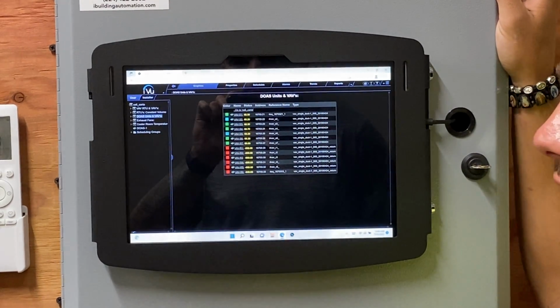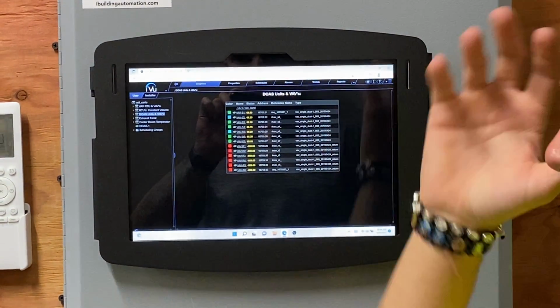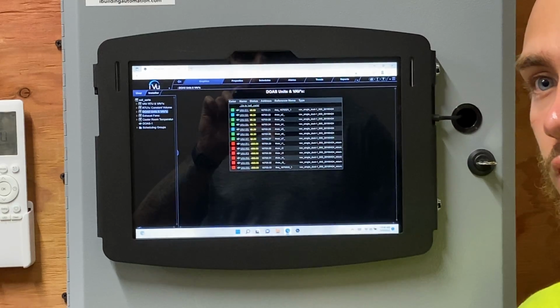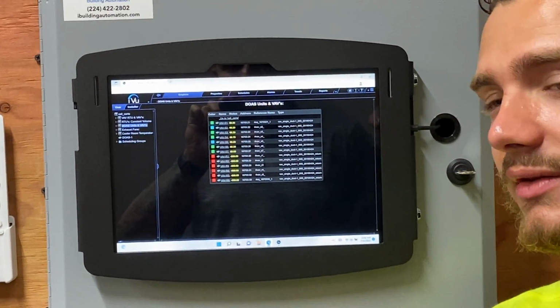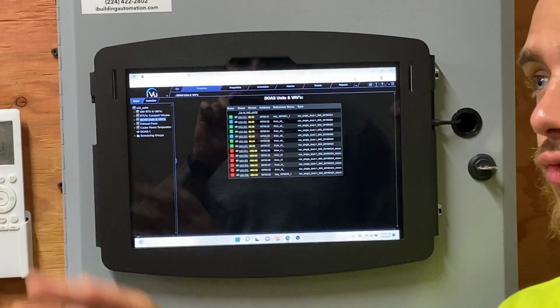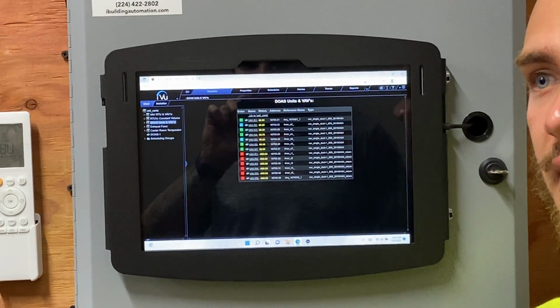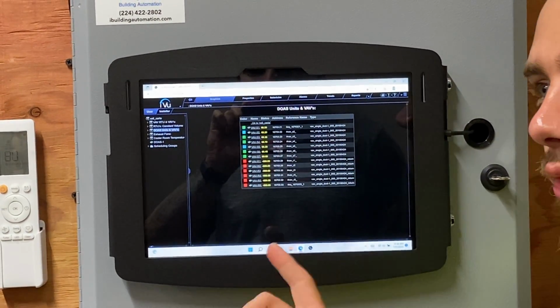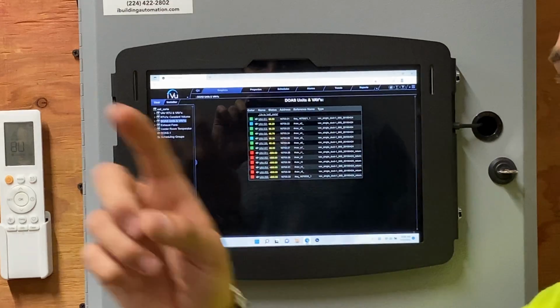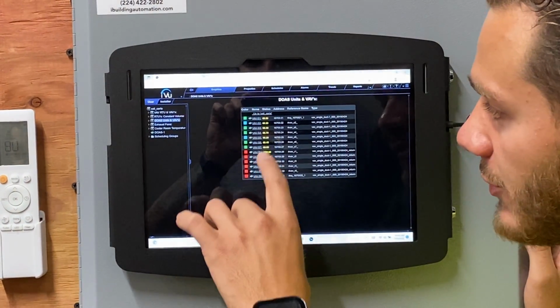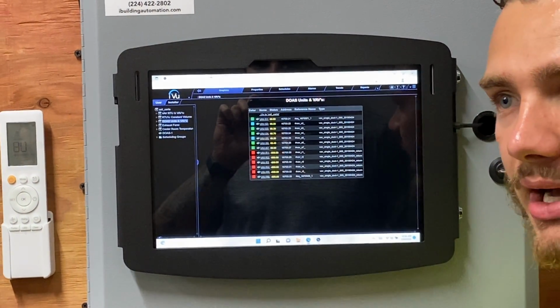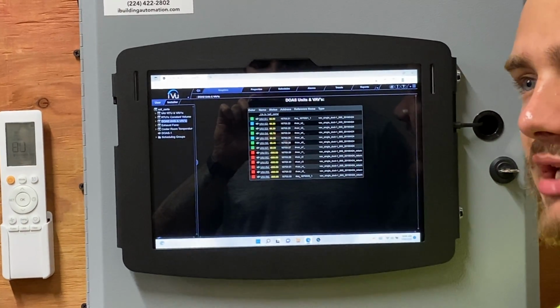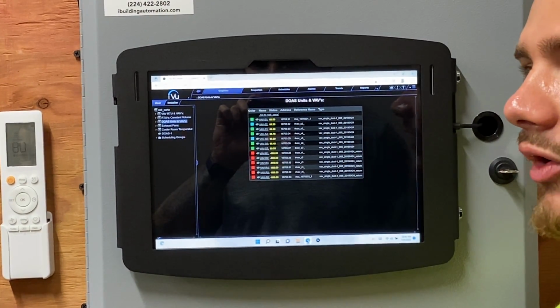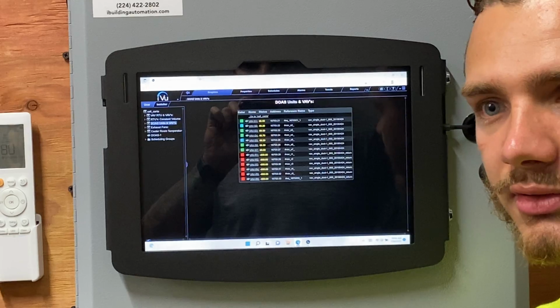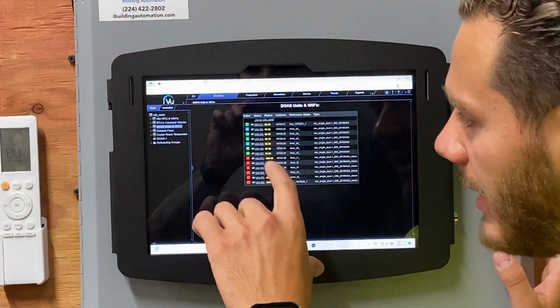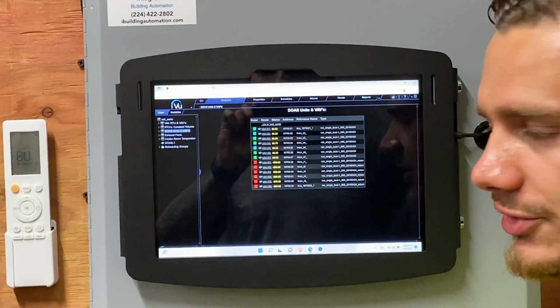So those are the return boxes. On that side, we're controlling the incoming air and the leaving air going back out of that room. Those rooms are extremely pressure sensitive, which is why you're seeing this. So on the return side, we're not actually working off temperature at all, we're working completely off pressure dependent controls, not referencing against space temperature.